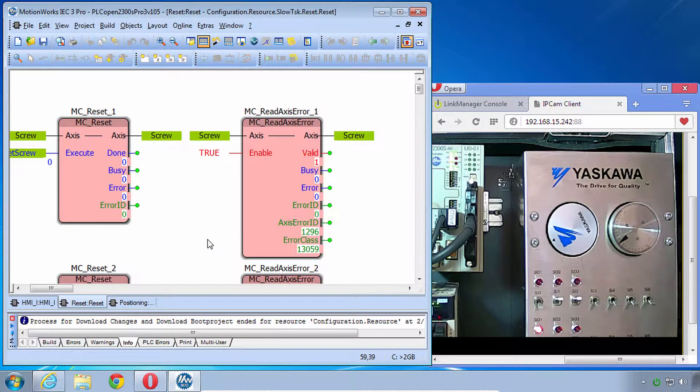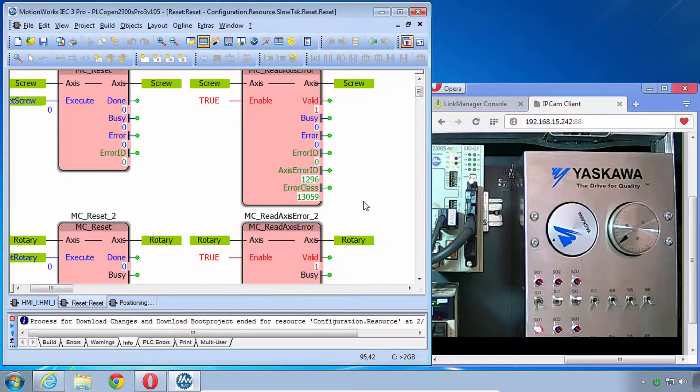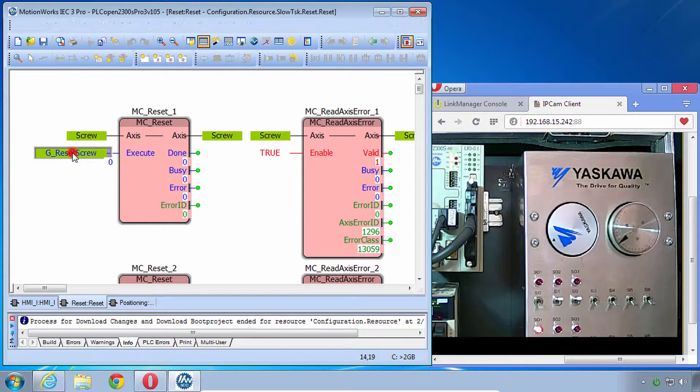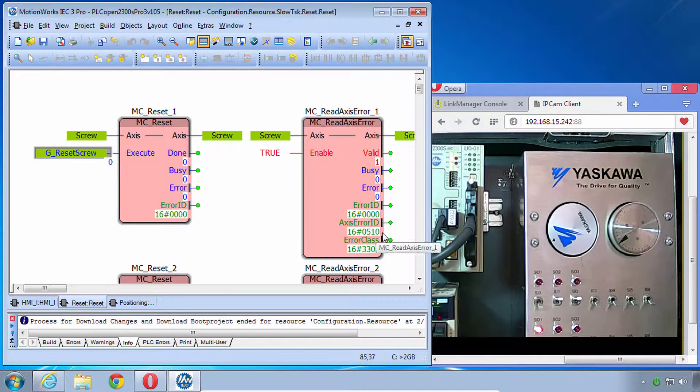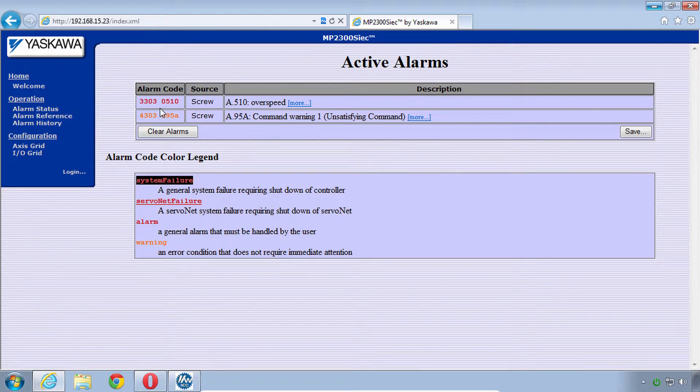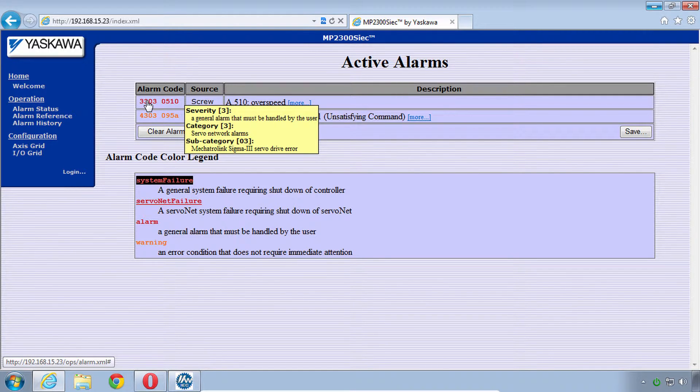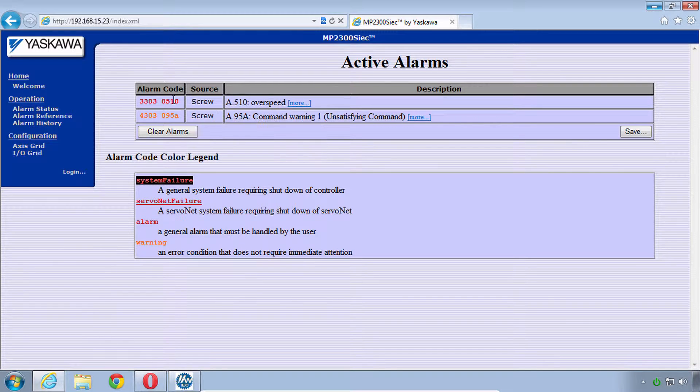And we can confirm that here in the reset POU. But curiously it says that the error ID is 1296. And that's because it's displaying a hexadecimal error code in decimal. But we can force this to display in hexadecimal. Just open any of these variables, like maybe G_Reset_Screw. And there's this value display which can be forced to hexadecimal. This is a software setting. And now we see in hexadecimal 16 pound 510 with the error class 3303. And since I did have the web page up, you'll see that those alarm codes are listed. And there's even a tooltip here 3303. So this is all vendor specific. These codes themselves are up to Yaskawa. And there's two parts to the code. There's the axis error and the error class.